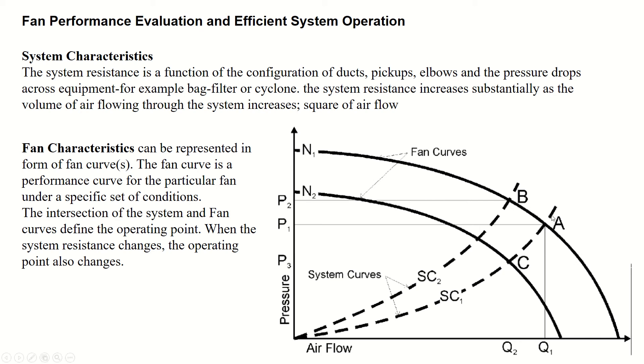There are three points — A, B, and C — and two fan curves: the first at N1 (higher RPM) and the second at N2 (lower RPM). At lower RPM, both pressure and volumetric airflow Q are lower. As airflow decreases, the pressure drop in the ducting system also decreases.